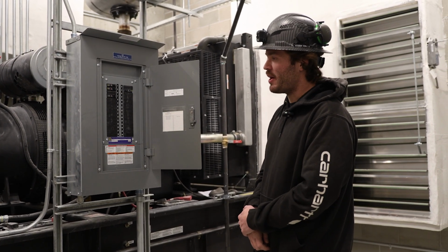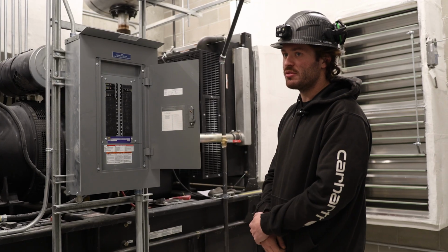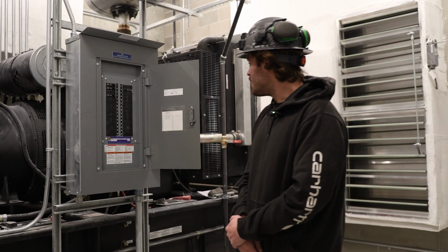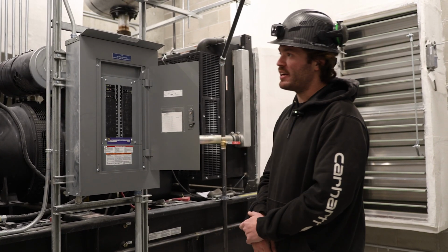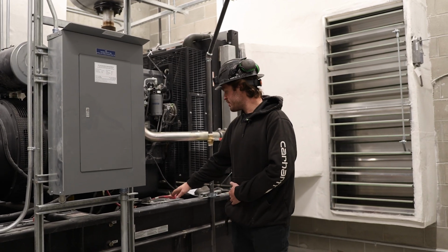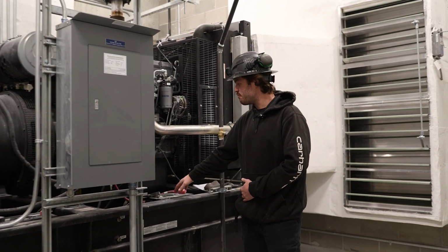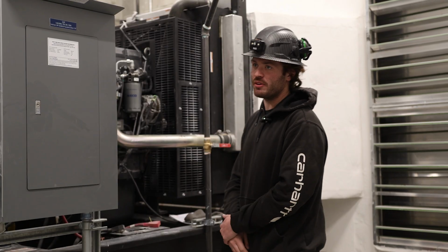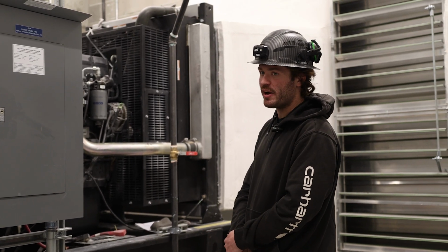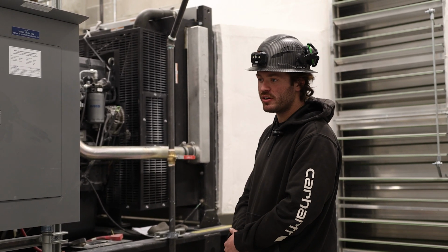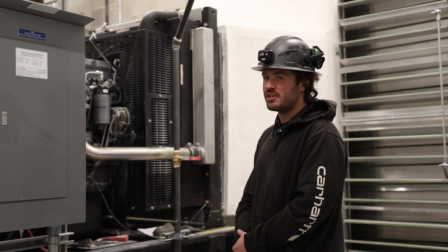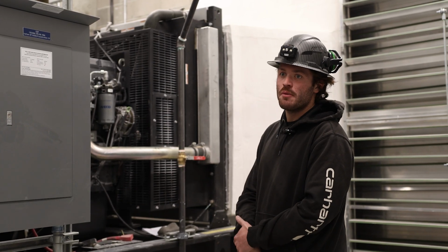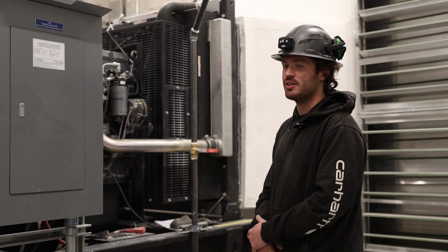So this provides us power for things like our battery charger, block heater, and in here is also for the building management system. Up at the side of the generator frame, on this side, we have both of our starting batteries. It's a 24-volt system, so it's using both batteries in series to start the generator. Battery replacements should be done approximately every 4 years, but they should be tested twice a year by code.